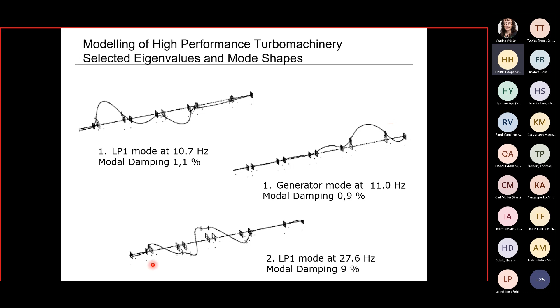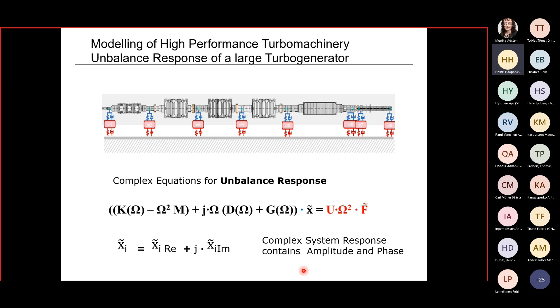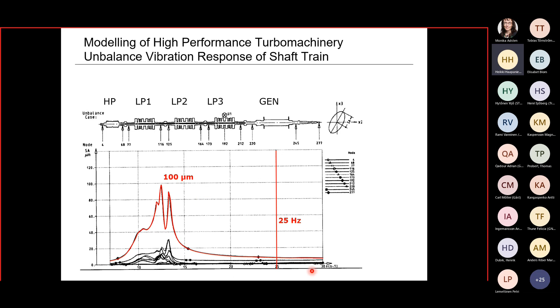The other part, which is of interest in the design and in the calculation, is the unbalanced response of large turbo generators. Now we have the model again here, but with unbalanced excitation, which is shown here on the right-hand side. And we can determine the response again. And this is expressed now in this curve, amplitude versus rotational speed. That's for a half-speed machine, running at 1500 rpm or 25 Hertz. And we see here, due to unbalanced forces, how the response of amplitudes looks like when we are in the range between 10 to 15 Hertz. We have some higher amplitudes up to 100 microns in this calculation. And the excitation was at this location. So we can do different calculations to see how the behavior is of our machine.